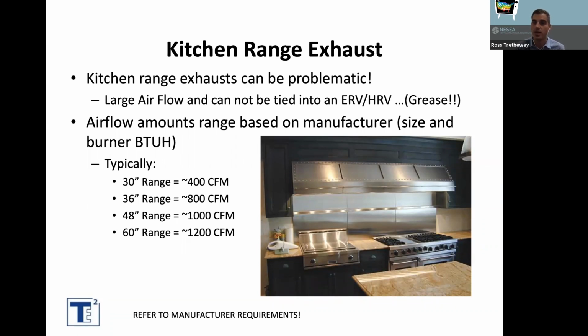A lot of people say, oh, I could tie the range right into my ERV or HRV. And that's really not the case. You've got grease, high temperature, and a lot of other issues that an ERV or HRV can't handle. It's not really designed for that. And I put some typical exhaust rates up here, and it really depends on the manufacturer and the type of cooking that you're doing, whether it's on a gas or induction, for example. There's going to be different rates.